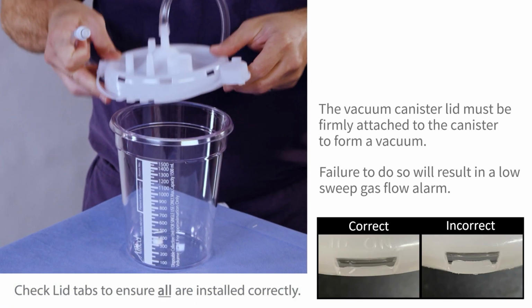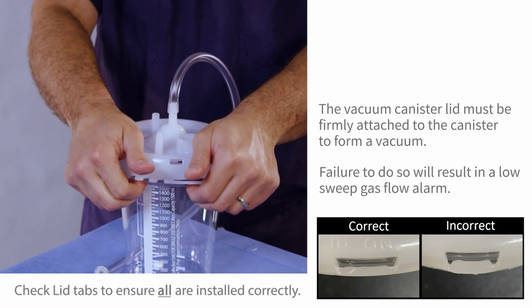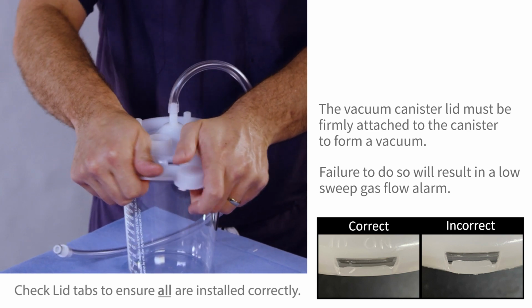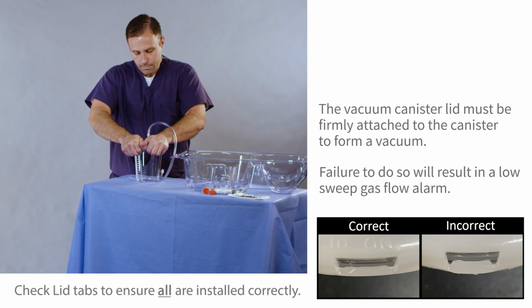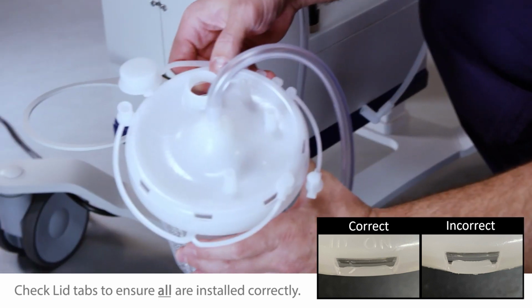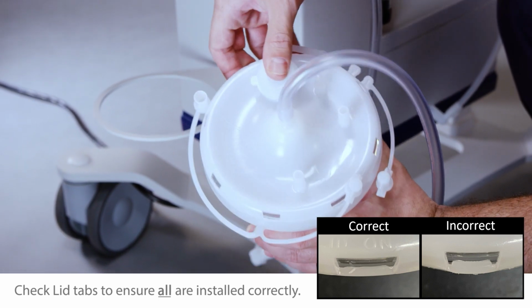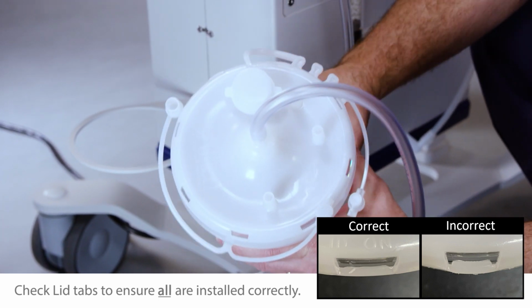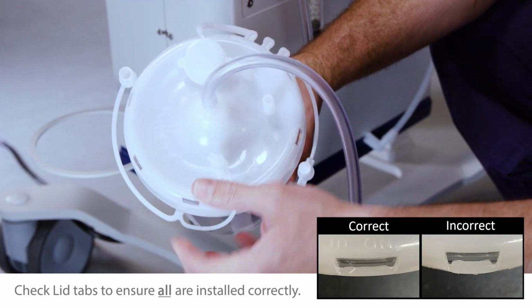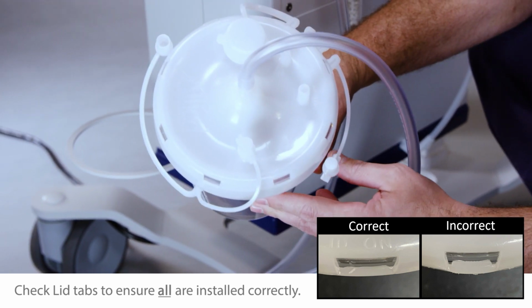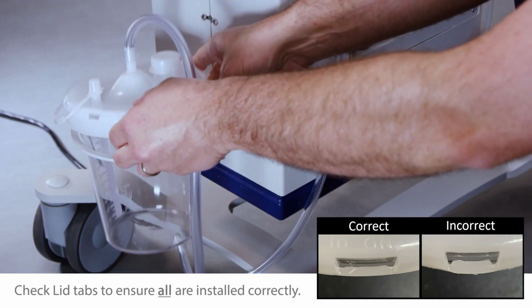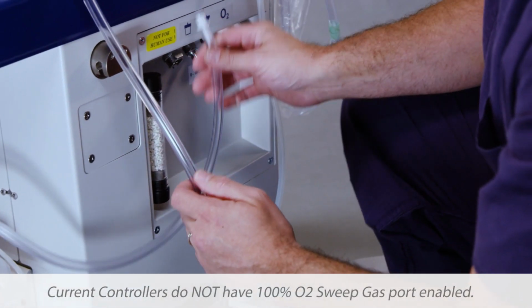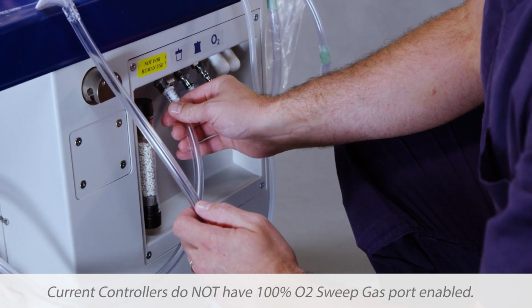Assemble a vacuum canister by firmly applying pressure around the circumference of the lid. Several clicks will be heard when properly secured. Cap the two unused ports labeled Accessory and Tandem. Then place the canister on the controller. Connect the sweep gas vacuum tube to the controller.